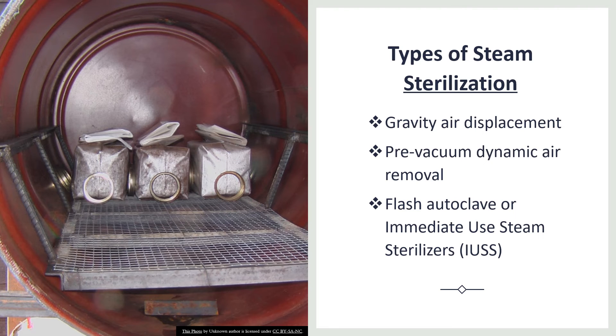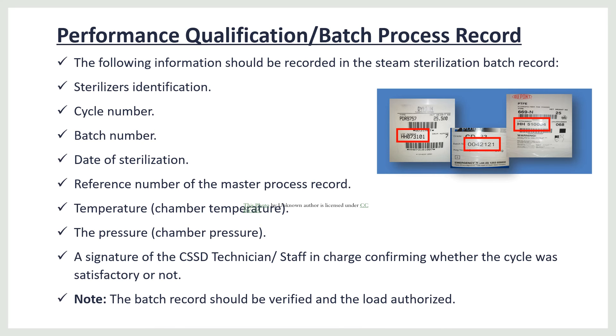Types of autoclaves include gravity type displacement, pre-vacuum dynamic air removal, flash autoclave, and immediate use steam sterilization. For performance qualification, the following information should be recorded: sterilizer identification, cycle number, batch number, date of sterilization, reference number of the master process record, temperature, pressure, and the signature of the operator. This batch record should be verified and the load authorized.